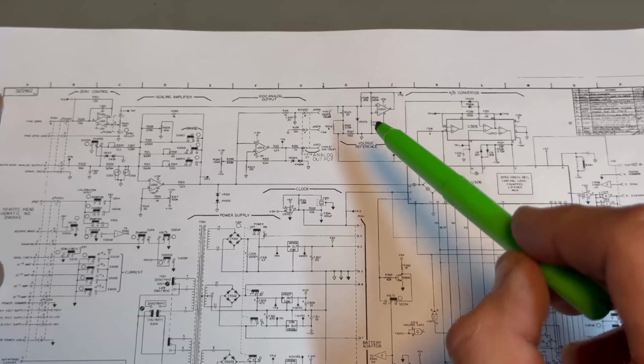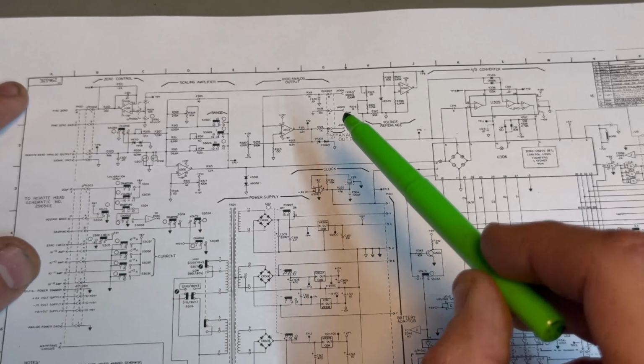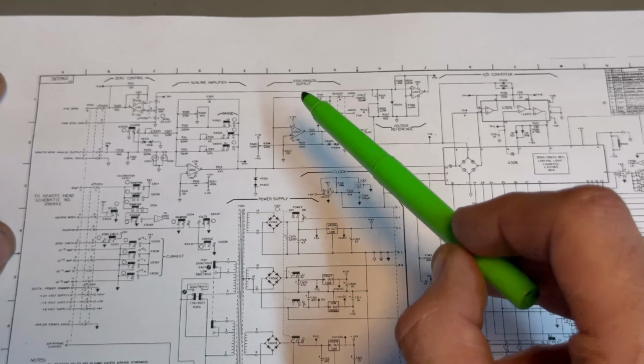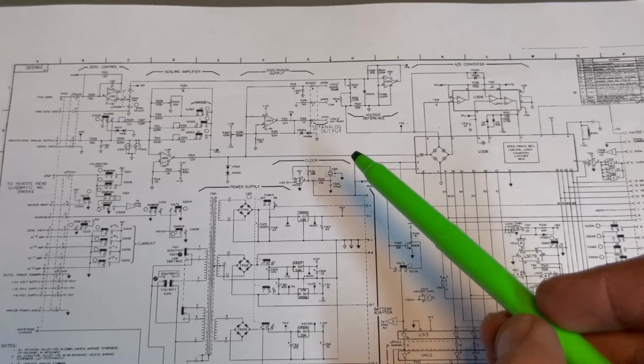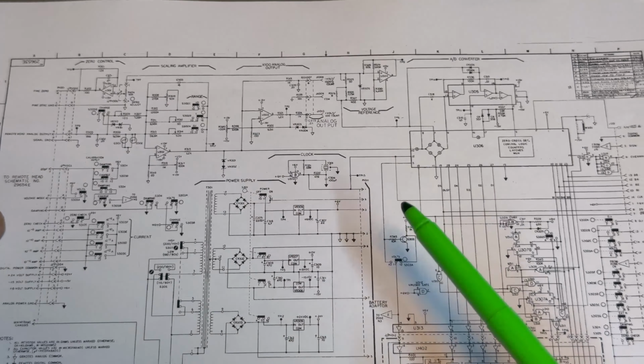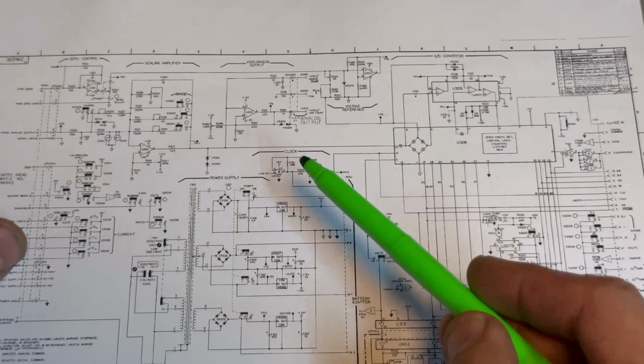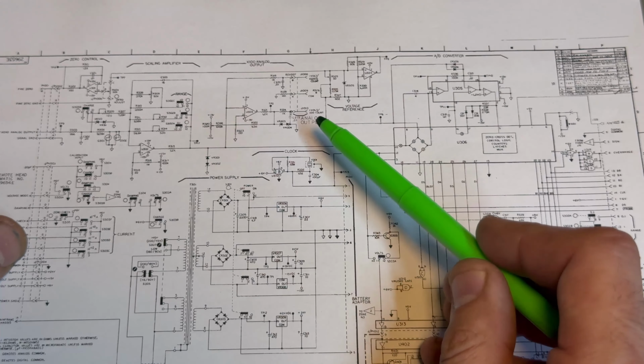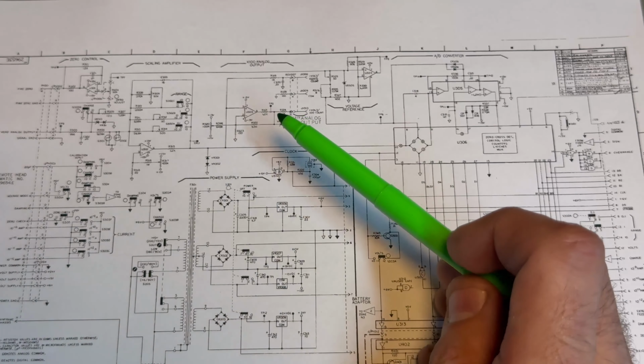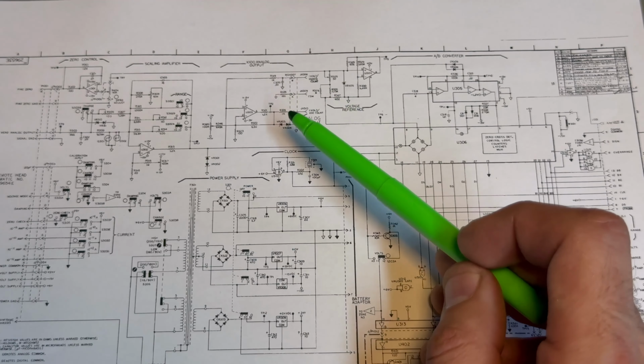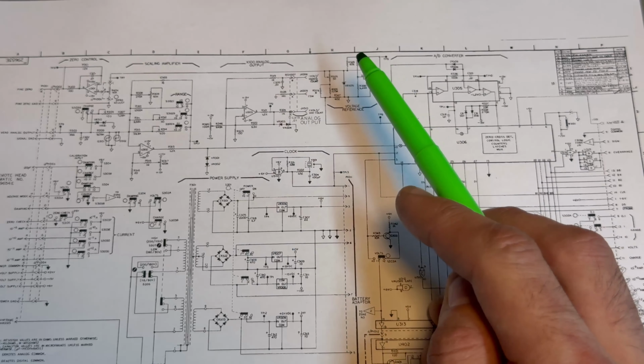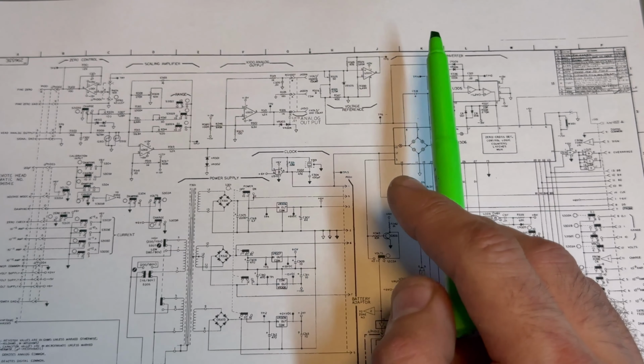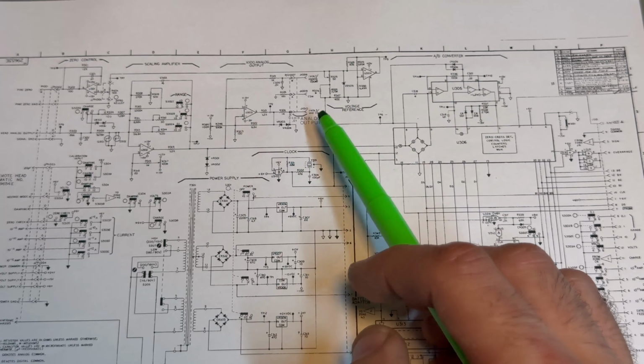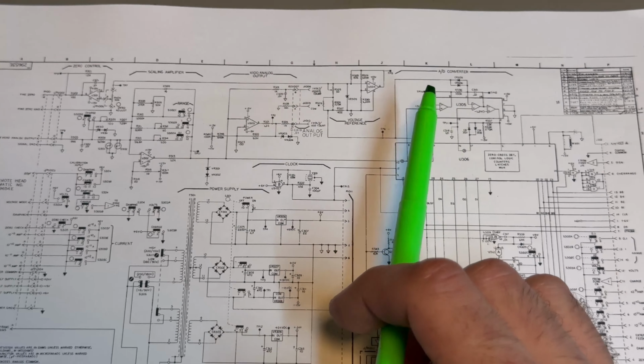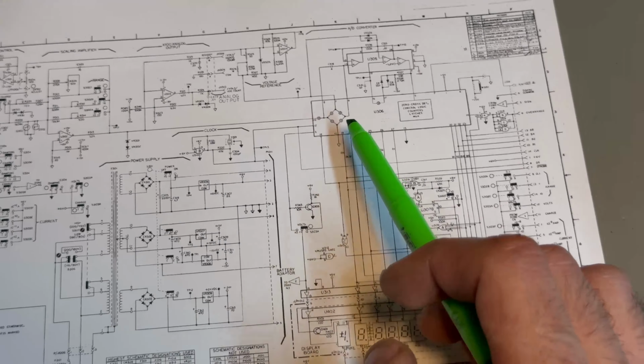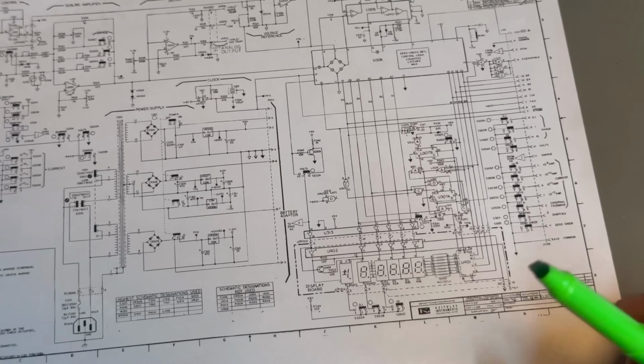Have a voltage reference with an op-amp and a Zener diode, and another times 100 gain for the analog output. I have no idea why you would want to use that, because it's 1 volt per 100 counts. I'm not entirely sure what it's for on all the ranges, but if you have 1 volt for 100 counts and you're looking at it through a 6.5 digit multimeter, then I think you'd be in electrons per hour or something like that sensitivity, which is absurd.